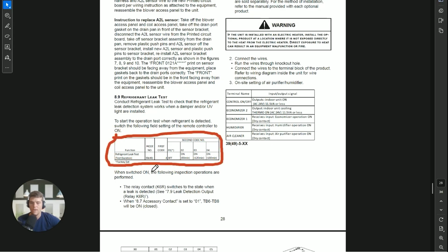So here we go, right there. So mode 49, right? We use this code for single indoor unit. 39 is for groups. Code 4, and then it's off from the factory. Should be, right? Shouldn't be tripped. I can turn it on for 60 minutes. I could turn it on for 120 minutes. I could turn it on for 180 minutes. This lets me test the unit as if it went off on a trip from sensing an A2L refrigerant in the system. Do the accessories do what they're supposed to?